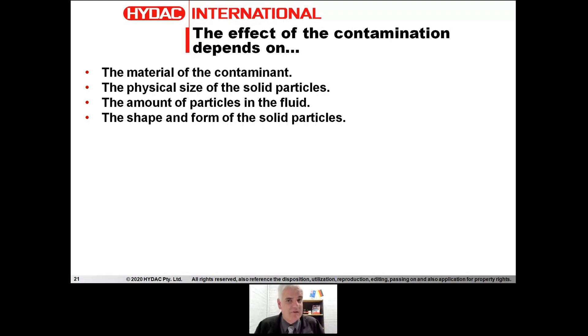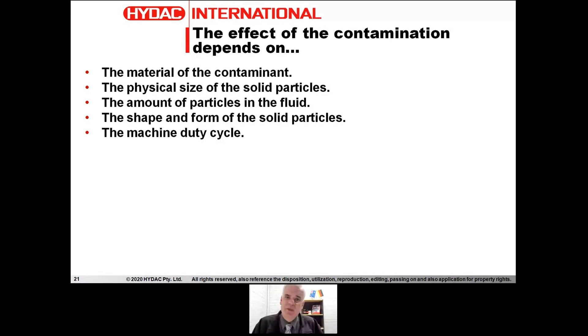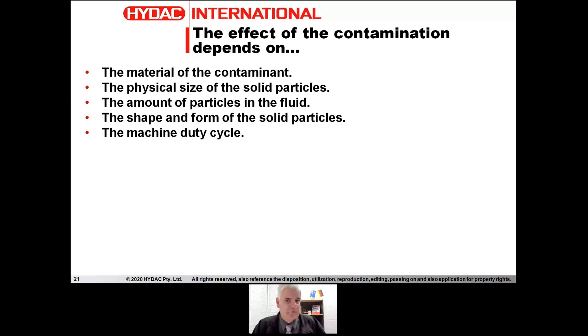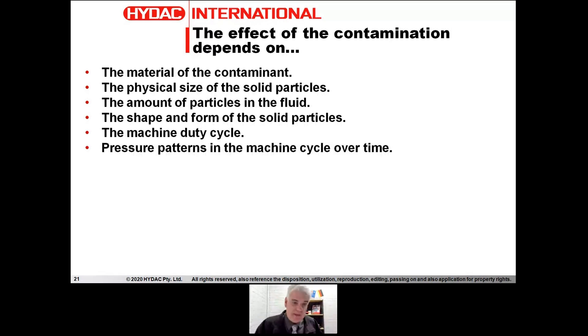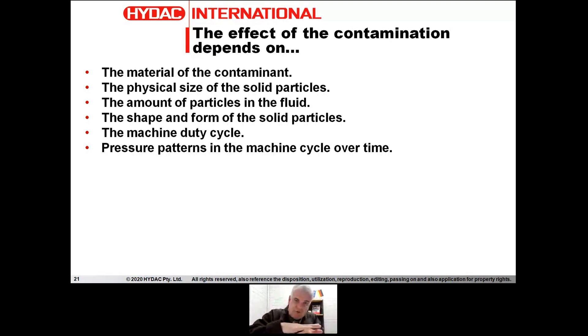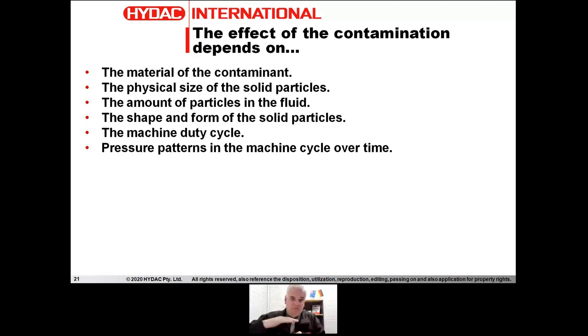Something hard in a jagged shape is going to do more tearing than a softer material in maybe the shape of a ball. The machine duty cycle matters — is it running 24 hours a day or five minutes every week? That makes a very big difference to how much contaminant you can tolerate. Pressure patterns in the machine cycle over time also matter: a machine working at higher pressure pushes internal parts together and closes the tolerance, so a higher-pressure system generally has a higher cleanliness requirement because the oil film is being challenged by that pressure loading.